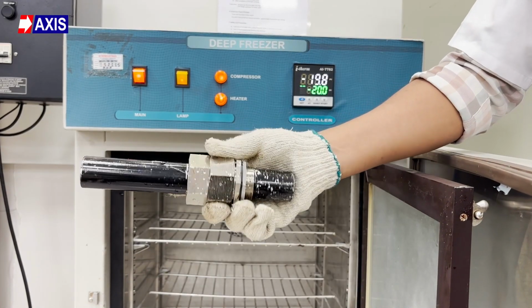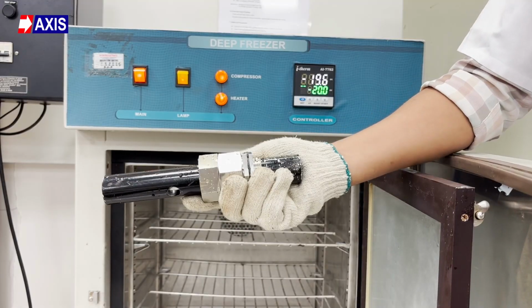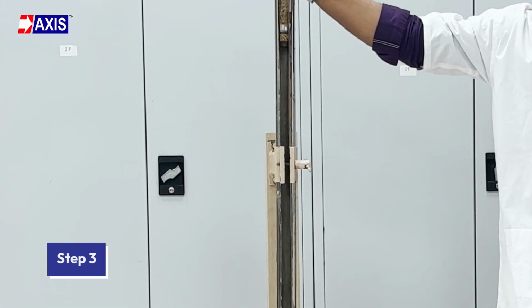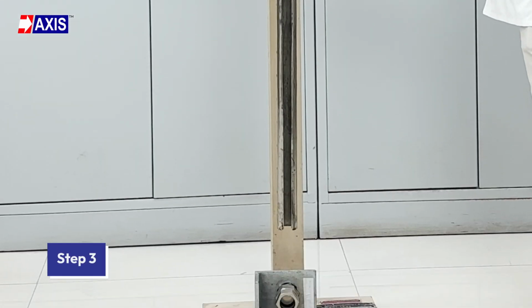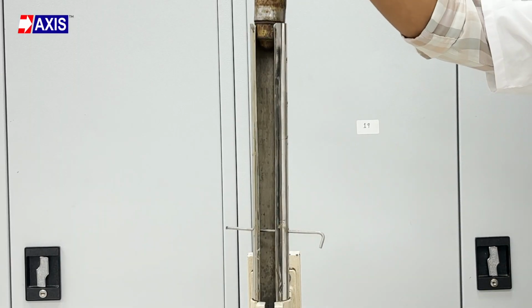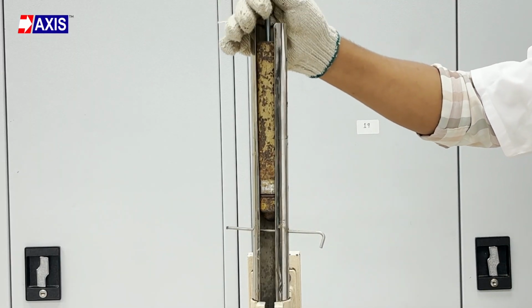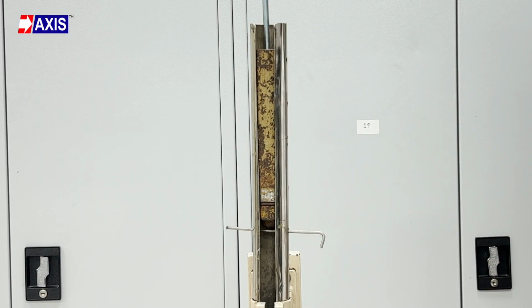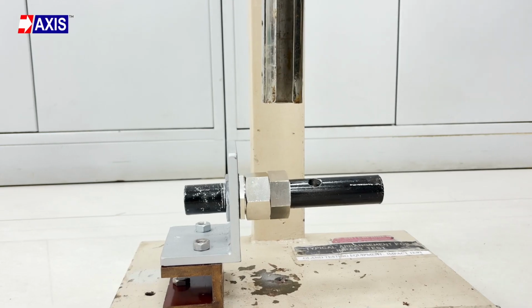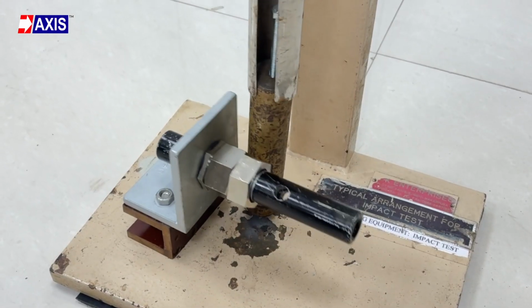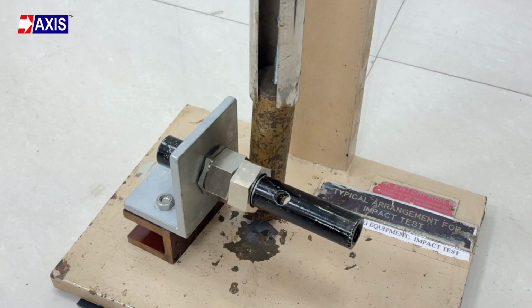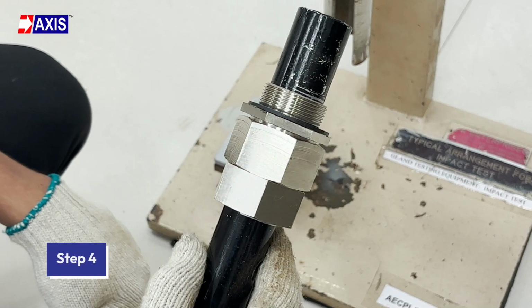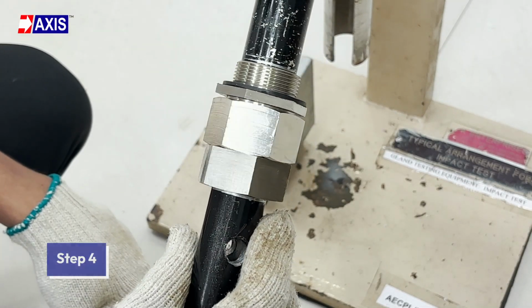Step 3. Using an impact testing apparatus with a 25mm hemispherical striker, release the striker from the defined height to deliver the required impact energy as per the gland size and category. Step 4. After the impact, check the gland.